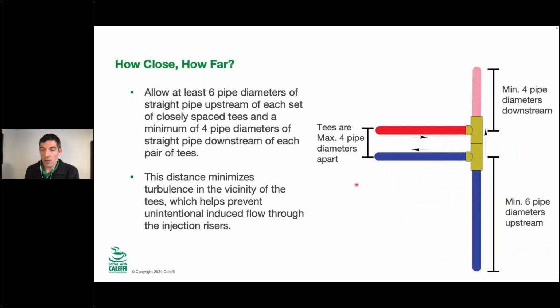Okay, closely spaced tees. That means what to people? How close, how far are we talking? I've seen a lot of boiler books over the years, going back 10 years to some of the installation instructions, and you would see stuff like maximum of 12 inches between, we'll say this is the boiler over here to the left, between the supply and the return.